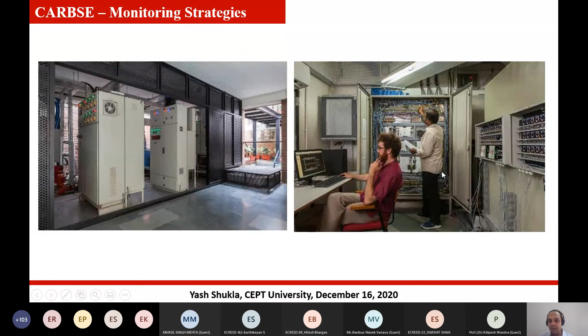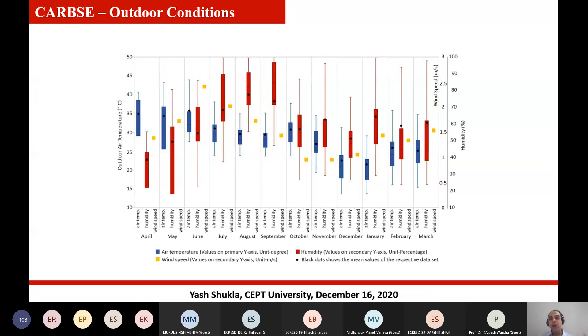So here I wanted to share what we have monitored in our building. This is outdoor temperature, the humidity range that you are seeing, as well as wind speed. You can see that we have observed temperature as high as 47, 48 degrees for this building, and 43 degrees, which is a blue bar. The humidity is as high as 100% when it's raining, and it happens in July, August, September, as you can see. And the wind velocity is as high as 2.5 meters per second, which is a very reasonable speed that you observe around Ahmedabad. So it has gone through a wide set of conditions.